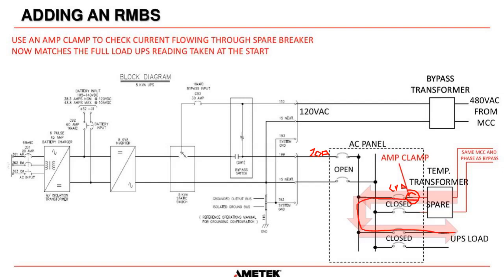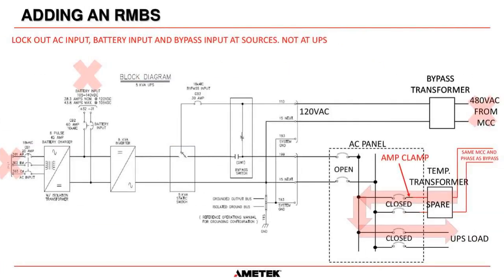And that way we know that we have maintained power to all of the critical loads. And once we see that, what we can do is disconnect or open, lock out, tag out the main bypass supply bucket that feeds the UPS. And then what you can see is we will have no AC input here. We've disconnected the batteries and locked and tagged them out. And now we have no power here, and we have opened this breaker, so we have no power here. So all of the terminals going to this UPS are now isolated, locked out and tagged out, and electrically safe. Okay. And that's just what this screen says again.